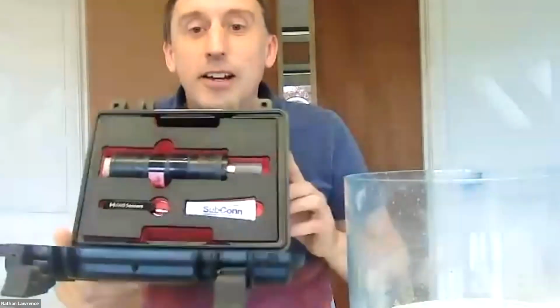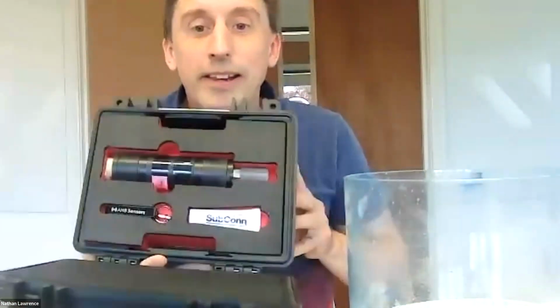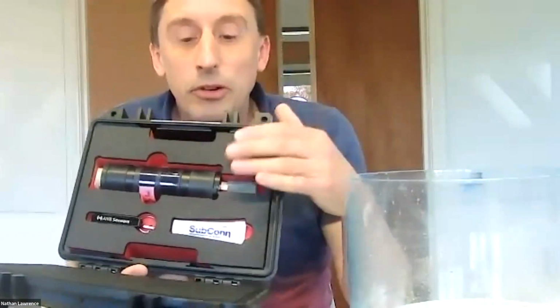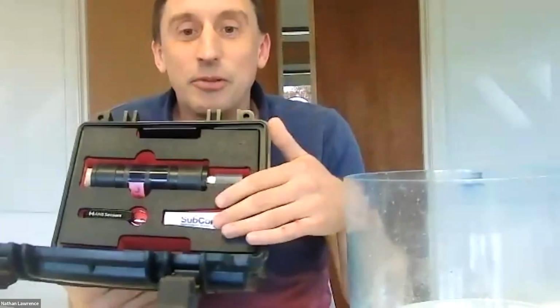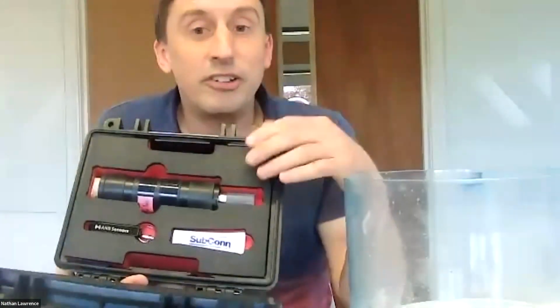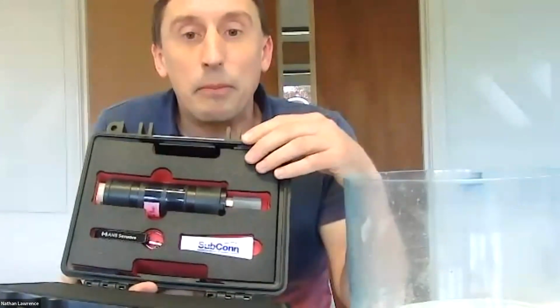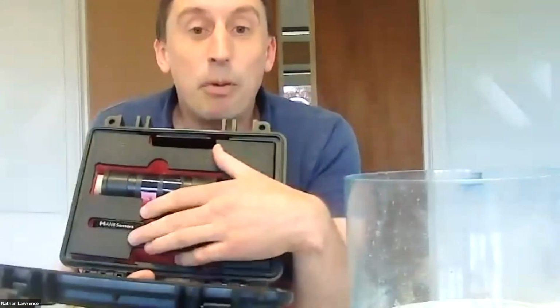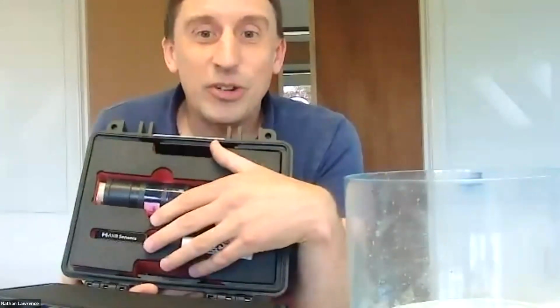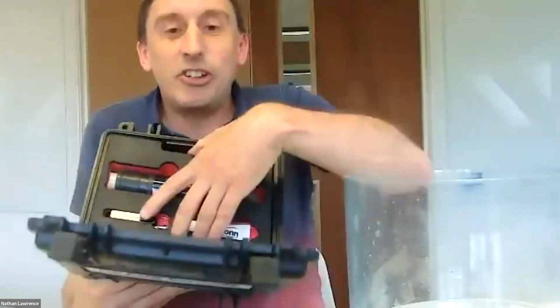I'm going to give you a demonstration, particularly choosing the OC300. That comes in a Peli case, a watertight Peli case, where in the system you get the sensor, some grease for greasing up when you change the transducer, which I'll talk about in a bit, and a bottle opener or extraction jig if you want to be sophisticated for replacing the transducer.